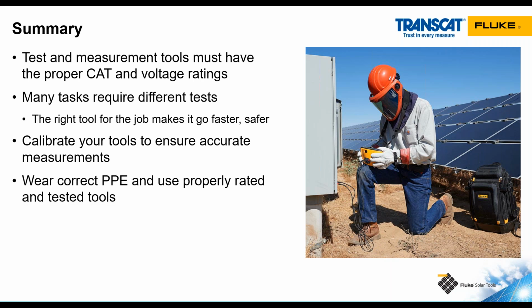And I didn't really talk about this during the presentation, but it's important to wear the proper personal protective equipment when we're doing testing. Often we are working on live systems, as we see in the picture here, and we need to have the proper equipment to protect ourselves in case there's a hazard. This technician has all the right equipment. They've got fire-rated clothing on. They've got electrically insulated gloves. They have an arc flash face shield and a balaclava. The only criticism that we have for this technician is he's kneeling, which is not a best practice because that knee touching the ground creates a much easier path for electricity than the insulated soles of his boots.